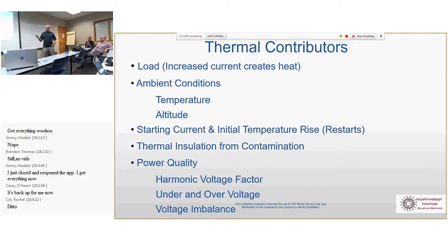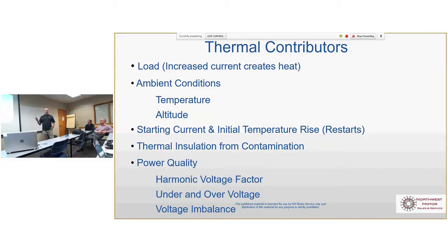Power quality is a big one. This is what we test for with the online test equipment you were asking me about. Power quality - harmonic voltage factor, under and over voltage imbalance - all that kind of stuff generates a lot of heat. That's one reason it's a big deal, and it's really hard to see most of that with just your fluke meter. Plus when you're using your fluke meter you're looking at one phase at a time, but we can look at all three at once, watch it real time. It really helps with troubleshooting. So keep that in mind.